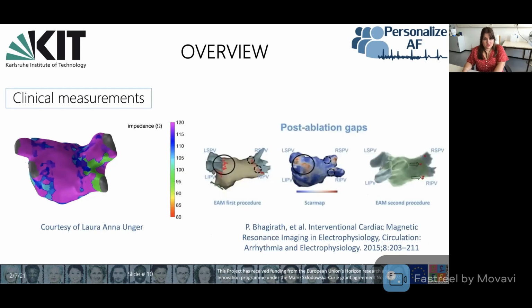Starting with the clinical applications, the basic application of impedance mapping is during the ablation procedure. Here on the left, we have a real clinical picture where we can see the impedance values in the atrium. And with impedance measurements, we can be sure that the ablation line is performed without gaps, as we can work without the previous time delay that we mentioned about the gadolinium.